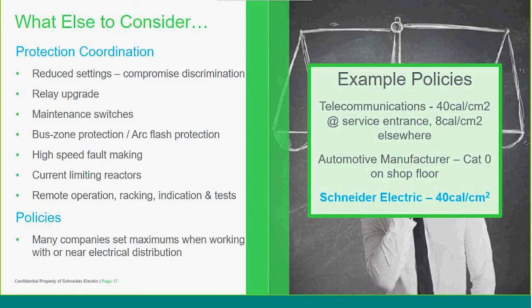As I mentioned before, there are some standard policies that people are starting to talk about now, where, depending on where you are in the power system, they try to define rules for the incident energy levels. At a control panel, some organisations say they don't want to exceed the lowest incident energy levels, and the level of PPE and training for that is minimal. However, there are parts of your distribution system which will be significantly higher. A good example, which a lot of people don't consider, is DC bus arc flash. DC arc flash is probably the worst because there is no current zero. So whenever you're working with batteries or battery strings in UPSs, arc flash is a very important consideration.